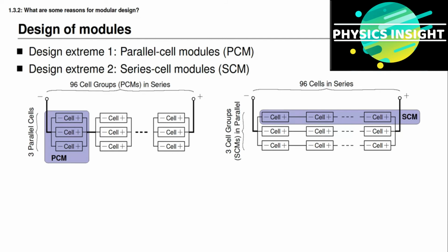But we could also consider the opposite design extreme, as shown in the second illustration. It has the same number of cells and the same overall general configuration, but they are wired differently. Here, we take 96 cells and connect them in series to make one module called a series cell module, or SCM. Then we take 3 of the SCMs and connect them in parallel, but only at the high voltage terminals, not at the individual cell voltage terminals.